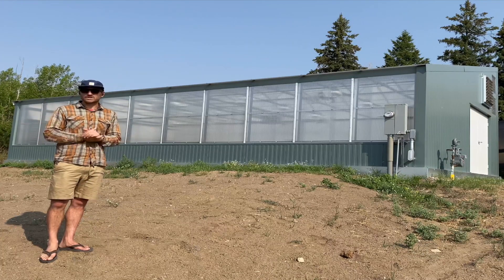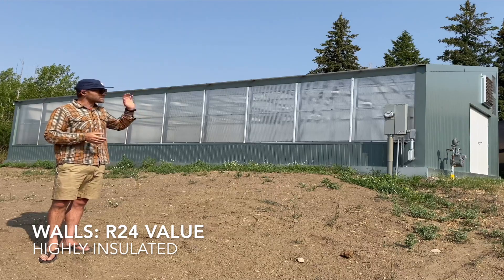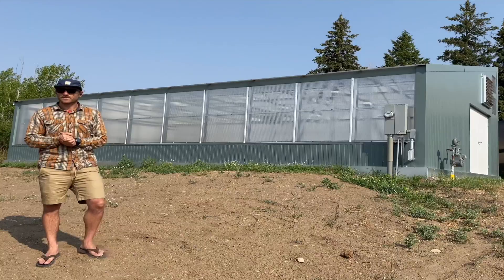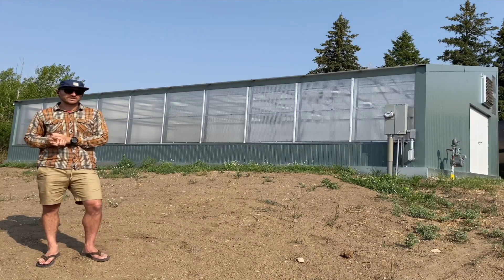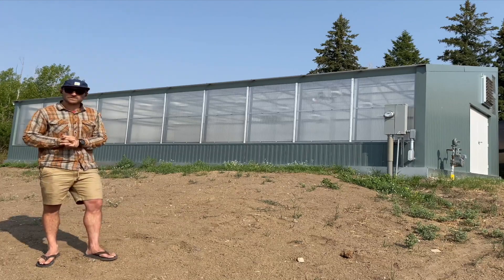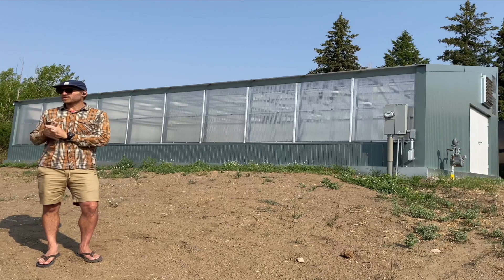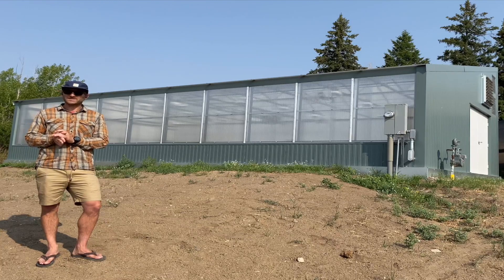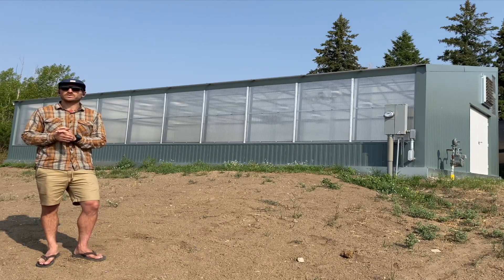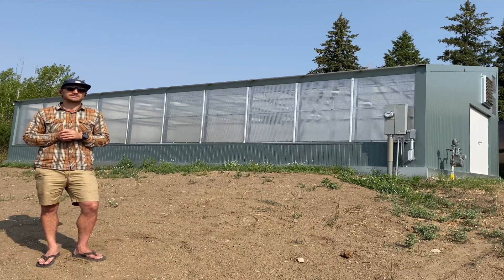Because it's highly insulated — it has three inch insulated metal panels — it's R24 along the walls. It's triple wall polycarbonate on the roof and the south wall. Three exhaust fans give us one full air exchange every minute if we need it. It has a ground air heat transfer system, or the GAHT system, that will help with keeping it cool in the summer, and most importantly, because they're mostly doing winter growing, cooling the greenhouse on sunny days in the winter. When the sun's out, they'll be able to maintain temps and prevent overheating with just the GAHT system alone.